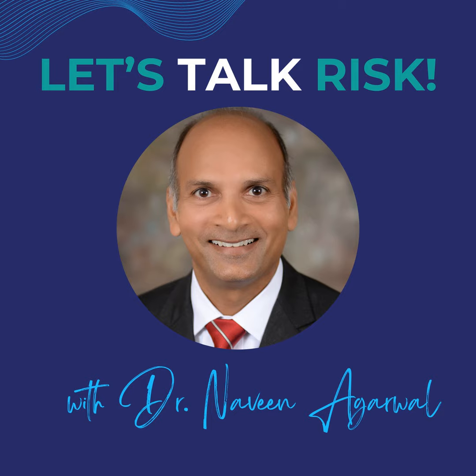So I would say I definitely favor the task analysis as being one of the founding documents. And normally when I've worked with medical professionals, it's like, here's how we intend to use this thing, and here's how we access, and here's what we do, even if it's in very broad strokes. And I bring that into the risk analysis.